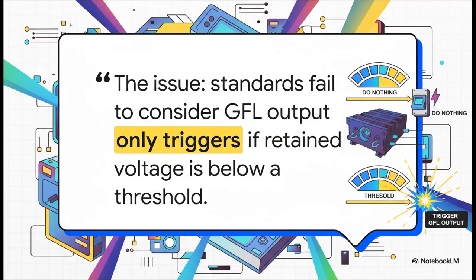That reactive current injection, the thing the inverter does to help support the grid during a fault, it doesn't just happen automatically. It only triggers if that retained voltage we just talked about drops below a very specific threshold. If the voltage dip isn't bad enough, the inverter's control logic just sits there and does nothing.